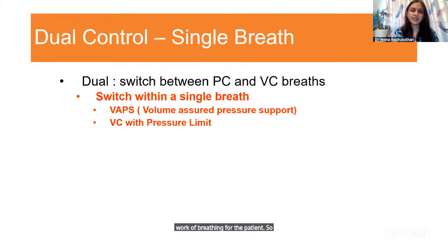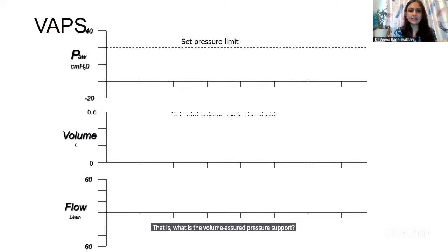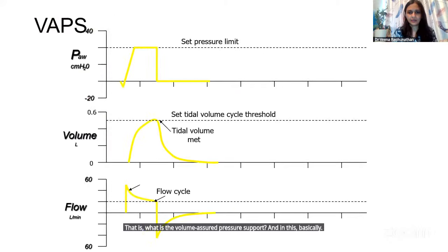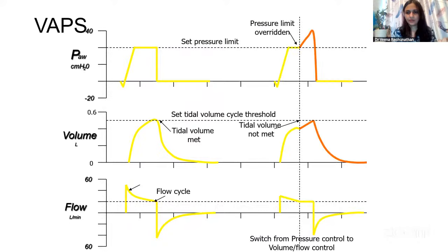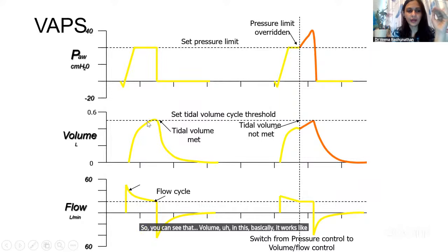So PRVC was breath to breath adaptive ventilation. There is something called dual control within a breath. That is volume assured pressure support. And in this, basically, it works like a pressure support. But in addition to that, we are setting a tidal volume.